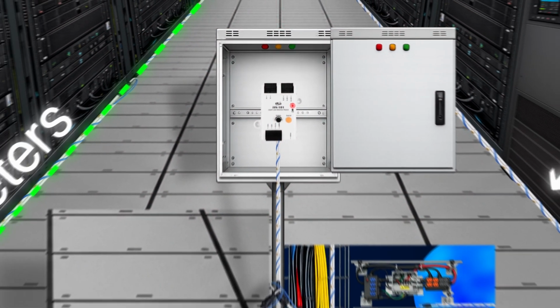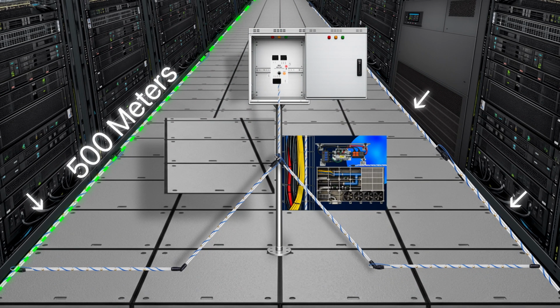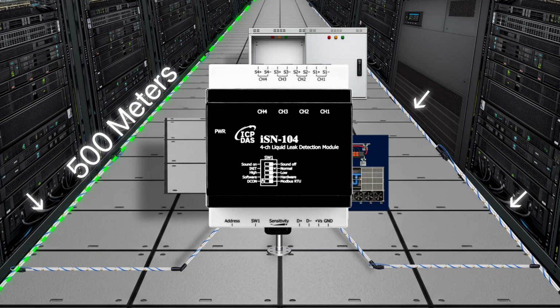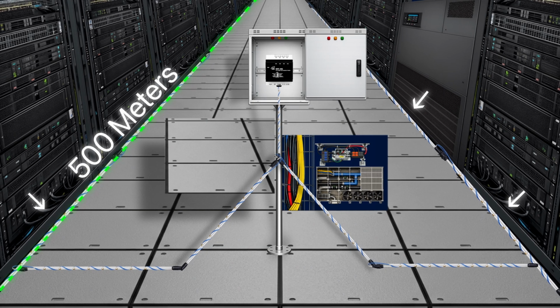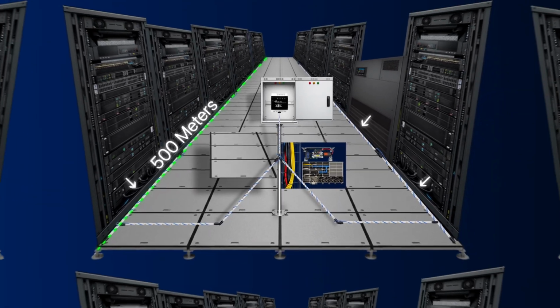For facilities that need to monitor multiple zones independently, which describes most data centers, the ISN 104 takes that capability further. It gives you 4 independent relay outputs from a single module, so you can divide your floor into distinct zones, assign each zone its own relay, and know immediately not just that a leak was detected, but exactly which zone it came from. That specificity matters when you're trying to respond quickly and get someone to the right location before the water reaches anything critical.